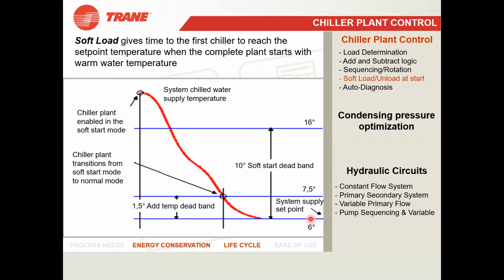And now I have to make you all understand the add logic. When in the office more people are there, occupancy is increasing and the load will be increasing. Then from 6 degrees it will again start increasing to 7.5 degrees. At 7.5 degrees it will fluctuate for some time, and if it stays at 7.5 degrees for 10 minutes, then one more chiller will be added. So what we get from the soft load is that it gives time to the first chiller to reach the set point temperature when the complete plant starts with warm water temperature. So that is an added advantage there.